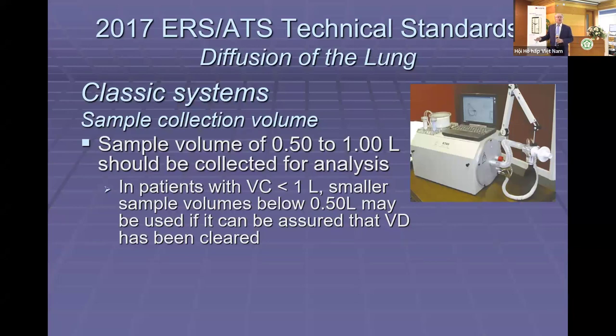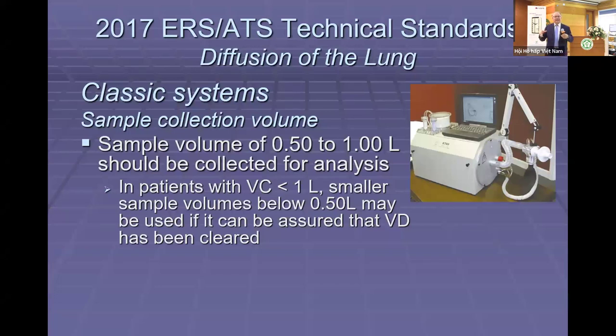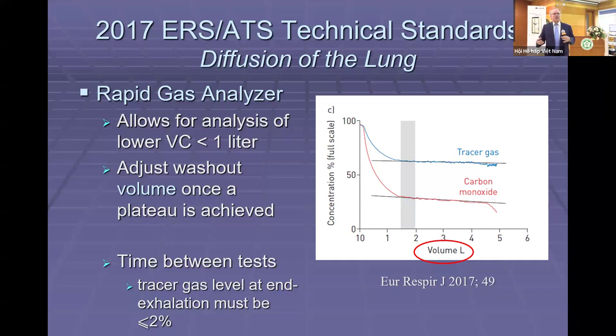This is a picture of a really old classic system — it has the bag for collecting the expired gas. It used to require a preset washout volume to get rid of dead-space air, and then a preset sample volume — that's the gas volume that was analyzed. Those are the classic systems. With the new rapid gas analyzers, you just wait until both the tracer gas and carbon monoxide reach a plateau. The dead-space volume and sample volume become irrelevant — you just need to reach a plateau.